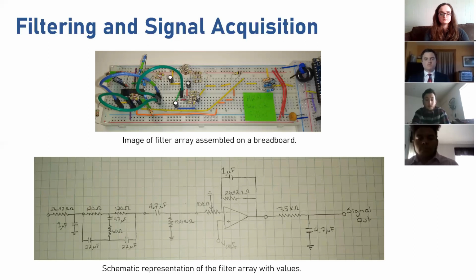Finally, a 4.5 Hz low-pass filter was added to further reduce high-frequency noise with a more reasonable max frequency of 270 beats per minute. And then the ferrite ring is the final filtering step, which uses the induction of eddy currents to numb the high-frequency peaks.